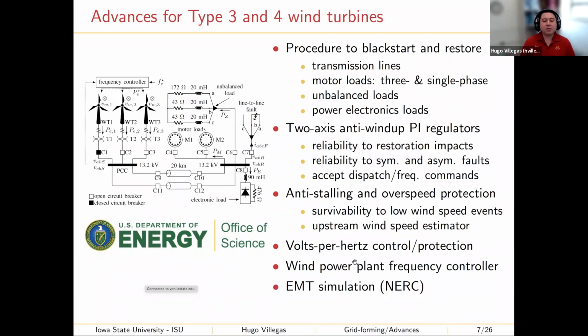Another very challenging aspect of this work was devising a frequency controller for the wind power plant. When we are restoring a system using gas turbines, we don't need this frequency controller, because the gas turbine usually works in an isochronous mode, in which frequency is almost maintained fixed. But when we are using several relatively small capacity wind power plants, we want to have some speed droop in order for the wind turbines to work in parallel.